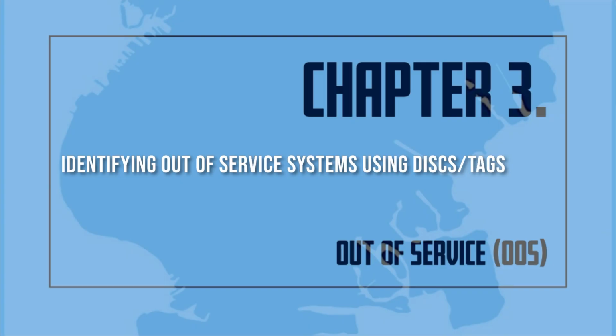Impairment coordinators/building owners shall ensure the placement of these tags by a master fire suppression piping contractor or a master licensed plumber as restricted. In addition, for an unplanned out-of-service condition, a disc, white or blue, shall be placed at all affected fire department connections to inform responding fire department units of the out-of-service condition. The impairment coordinator/building owner shall ensure placement of these discs by a master fire suppression piping contractor, a master licensed plumber, as restricted, or fire department units. When the condition has been corrected, the discs shall be removed immediately.